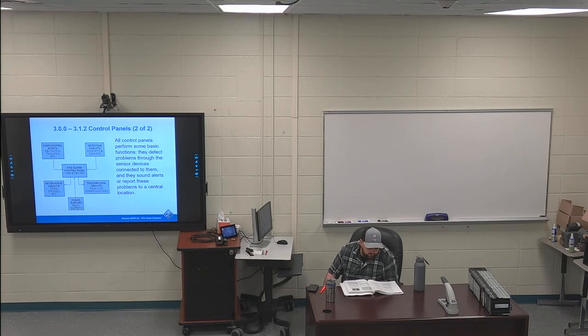Skip a sentence in the top right of the page, and the next sentence is highlighted. As defined by NFPA 72, standby time for operation of the system on secondary power must be no less than 24 hours for central, local, proprietary, voice communications and household systems. So that is for household systems.